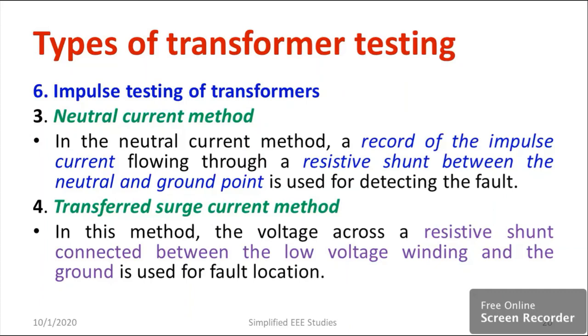Moving on to the neutral current method. A record of the impulse current flowing through a resistive shunt between the neutral and ground point is considered for detecting the fault. Based on the waveforms, you can identify whether a fault has taken place or not. That method is known as the neutral current method.